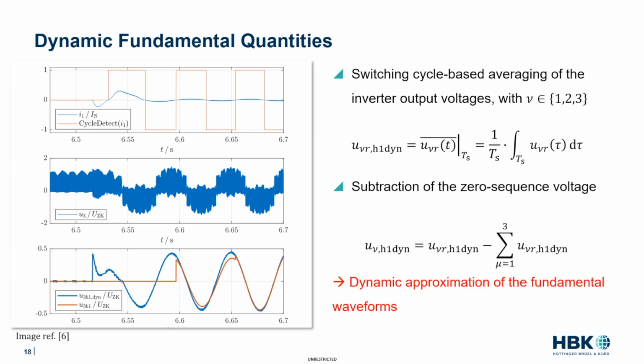Standards for power calculations and fundamental definitions depend on the fundamental cycle, and in a strict sense are only defined for periodic quantities, i.e. steady state conditions. During startup there is no steady state, so the conventional method isn't strictly defined. Problems arise because the frequency increases continuously, zero crossings aren't at the correct position, and steps occur at the beginning and end of periods since the voltage amplitude also increases continuously. You can instead choose the dynamic approximation to get better results, including transient peaks.